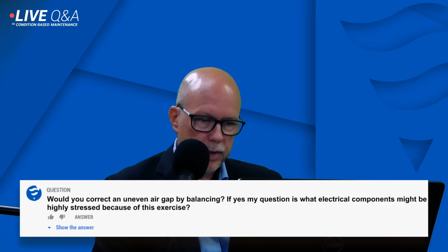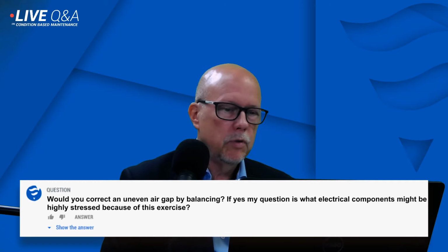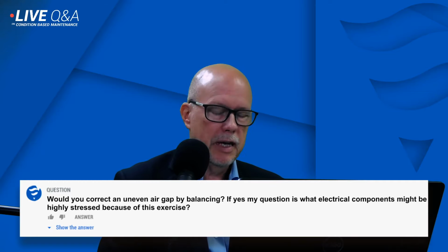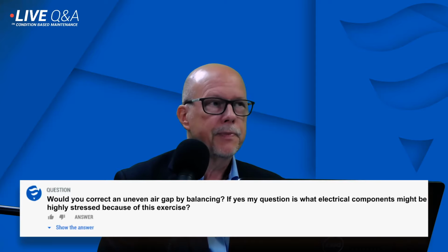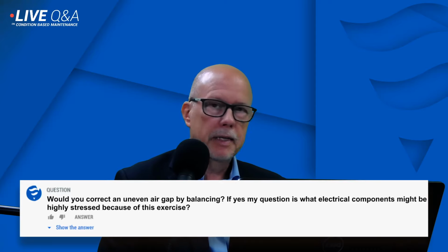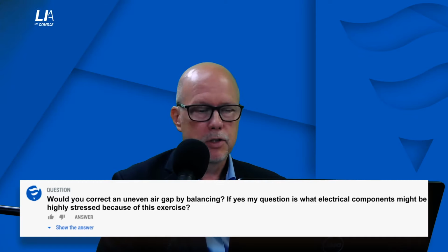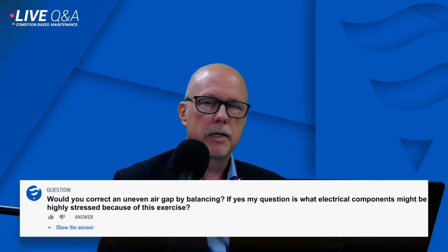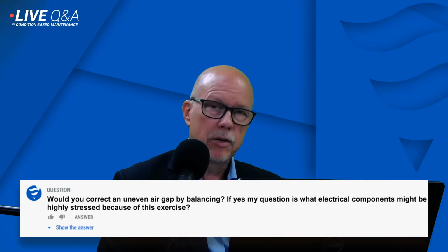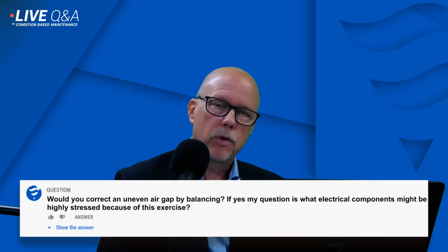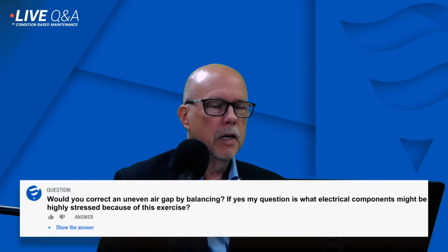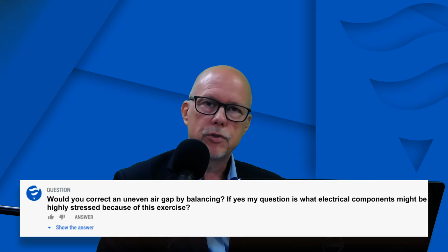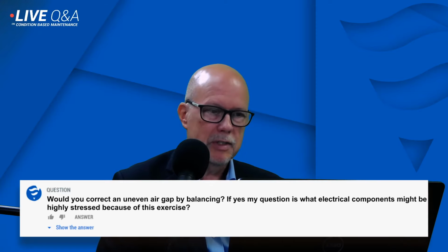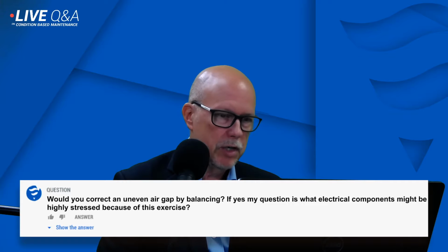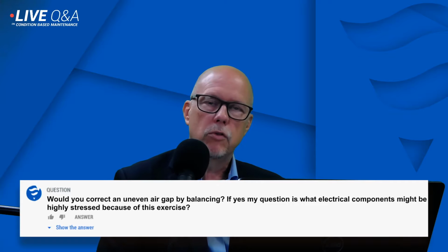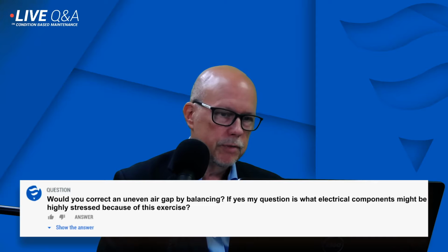So you create this vibration that will eventually cause damage to the components of the rotor. What you also have is that the magnetic flux being stronger where the air gap is smallest, it also applies much higher stresses to the stator core than what it was designed for. The magnetic intensity is much higher. You will probably see more stress applied to the stator bars because the flux is higher, so you can expect to see higher stator bar vibration. You will see eventually overheating and all kinds of potential issues.